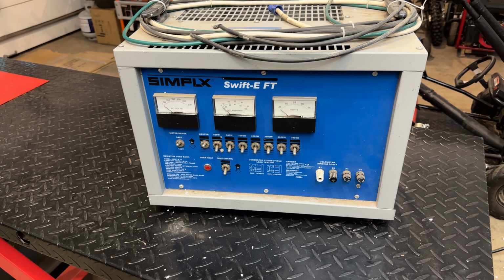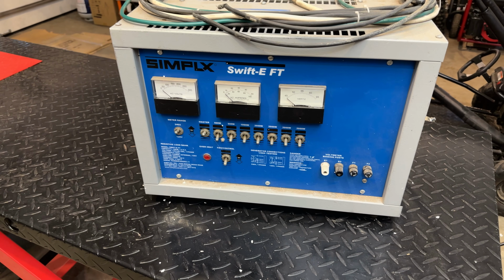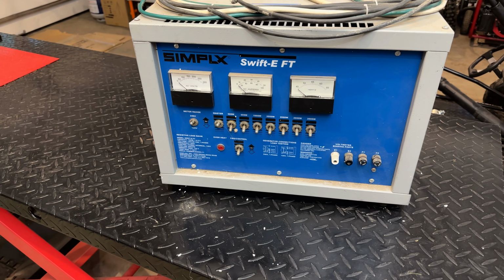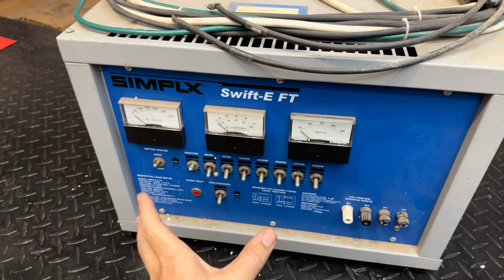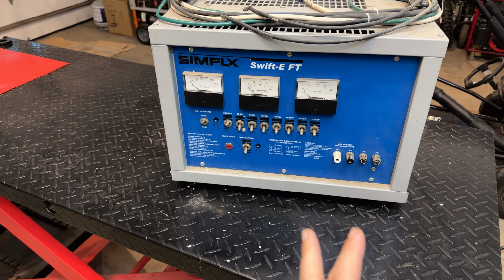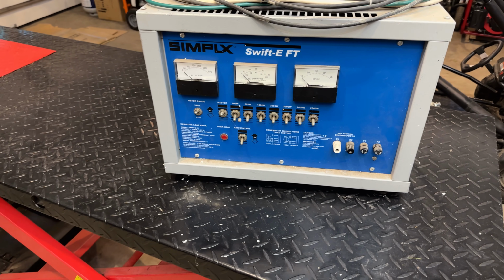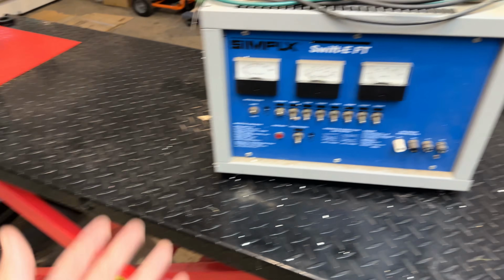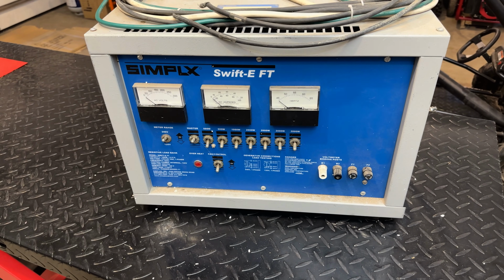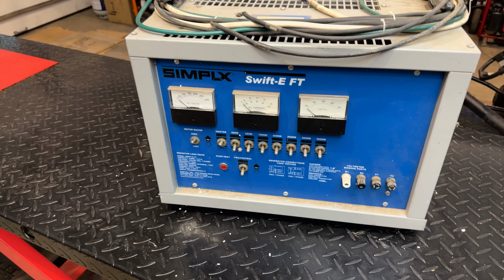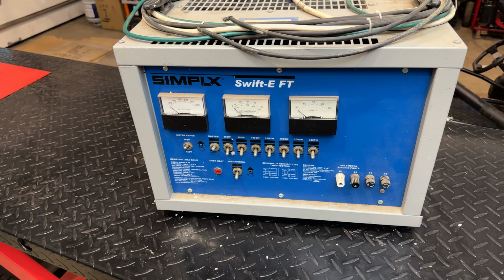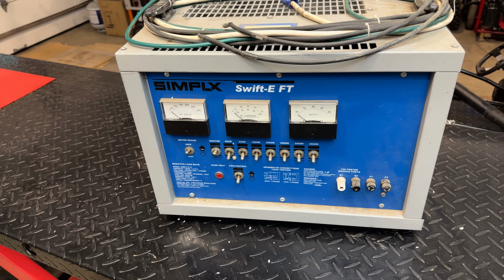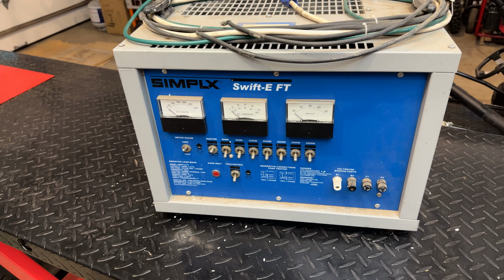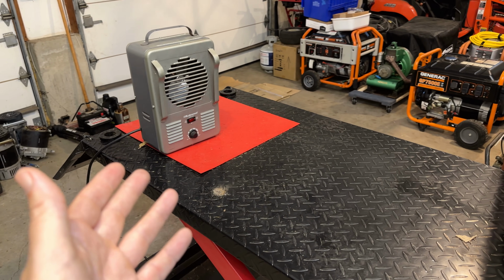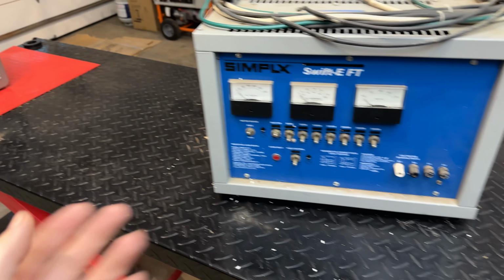If you guessed a load bank, you'd be right. This is a Simplex load bank. It's rated up to 10,000 watts of load in 500 watt increments, so we can test anywhere between 500 and 10,000 watts depending upon what generator we are testing. It's pretty basic, just a resistive heater, very similar to a space heater. The big difference is the price, and of course it's a professional grade piece of equipment. Now, these brand new are around $4,000 or $5,000, and that I couldn't justify. Even used, they're still about $2,500. And when you can get a space heater for 30 or 40 bucks, then yeah, it's kind of a no-brainer.